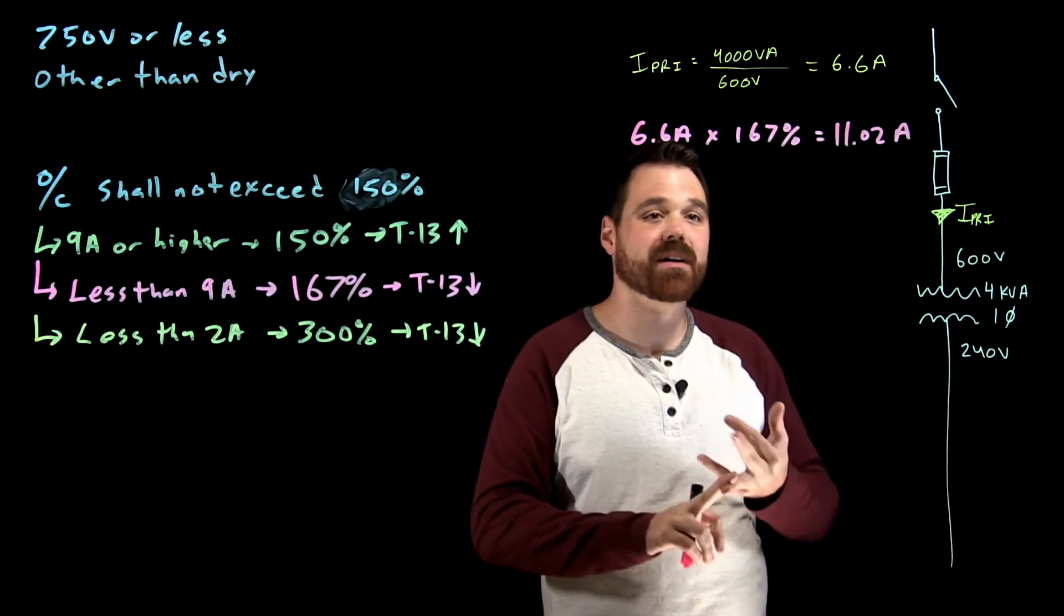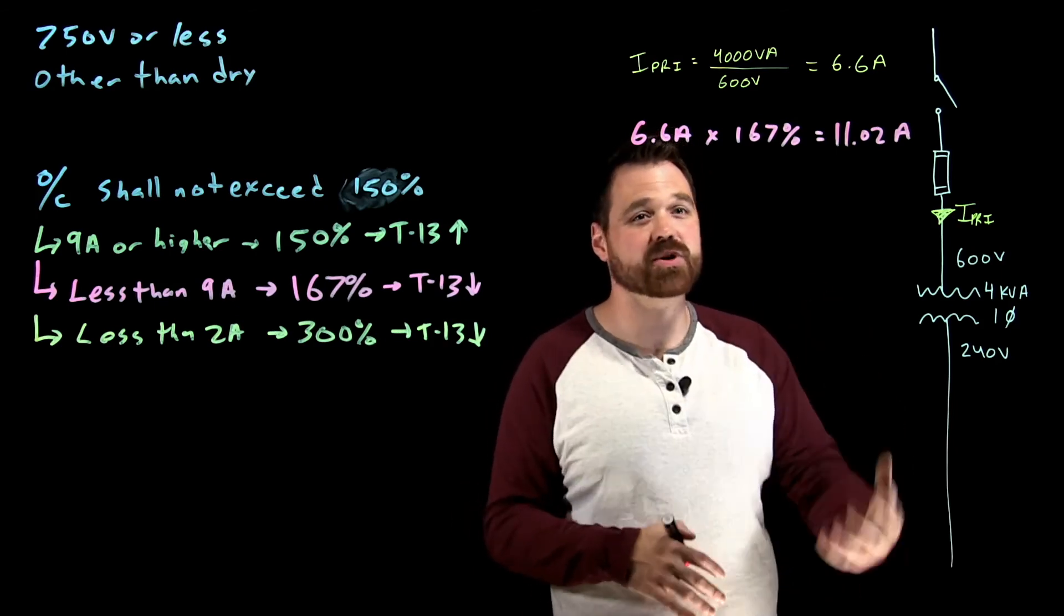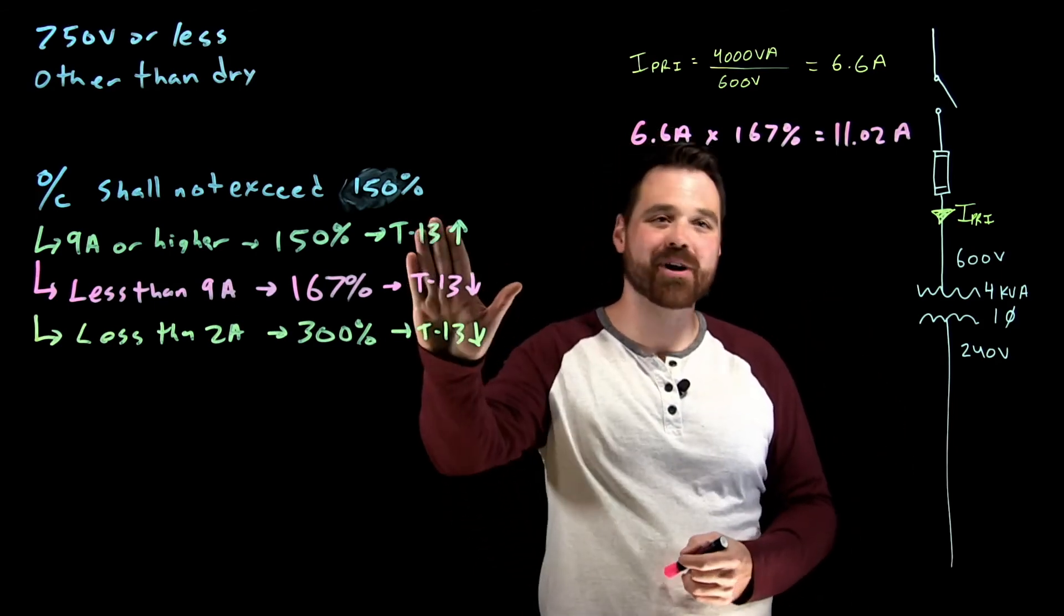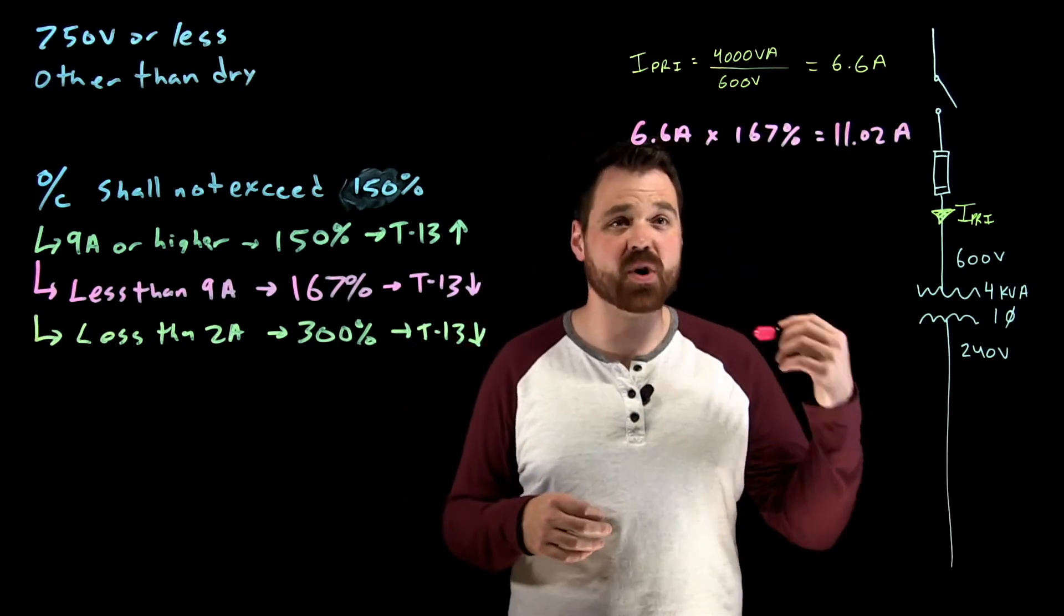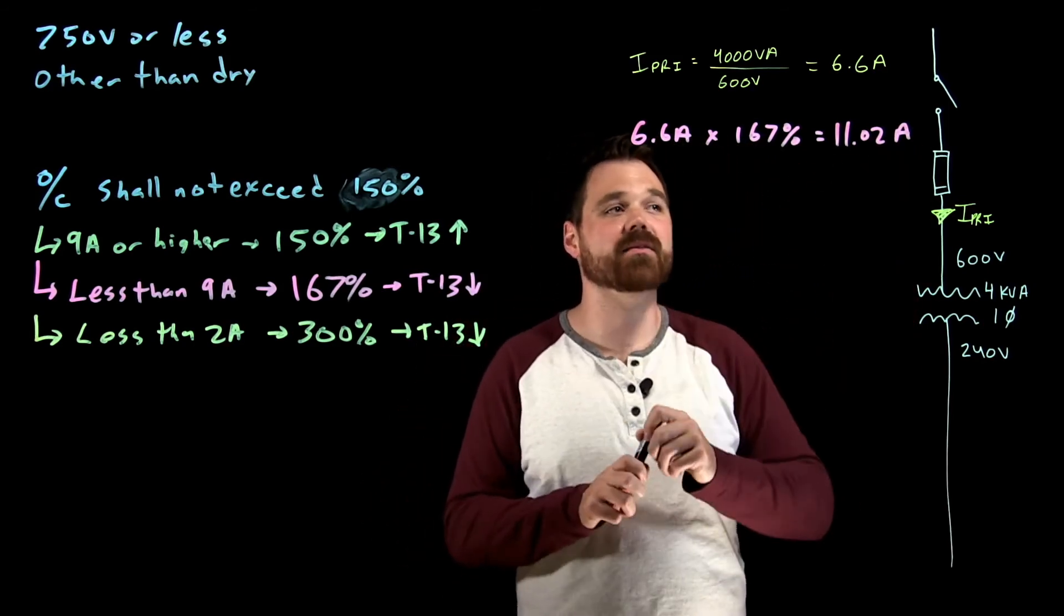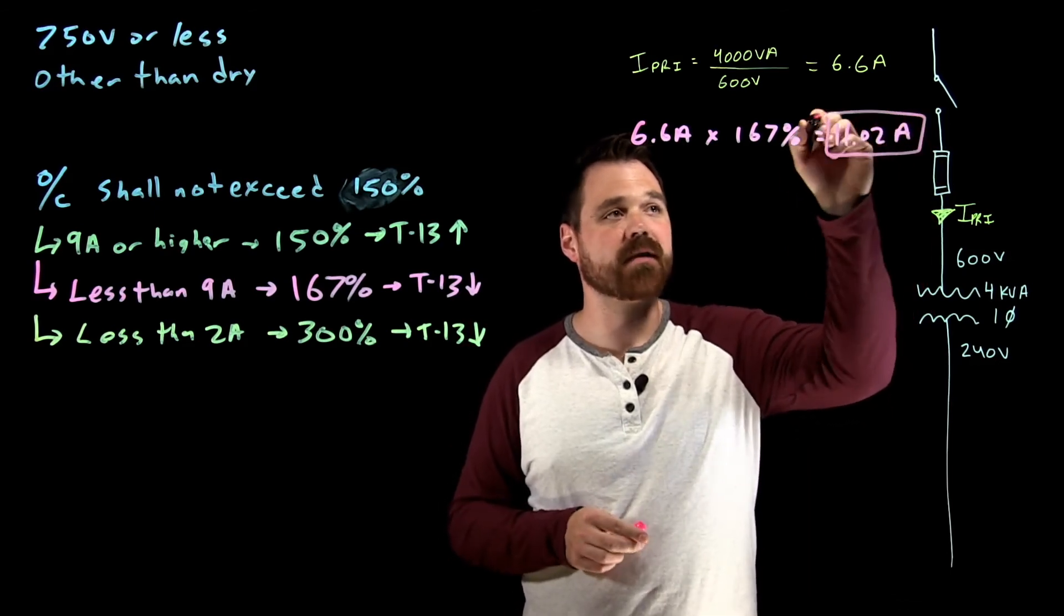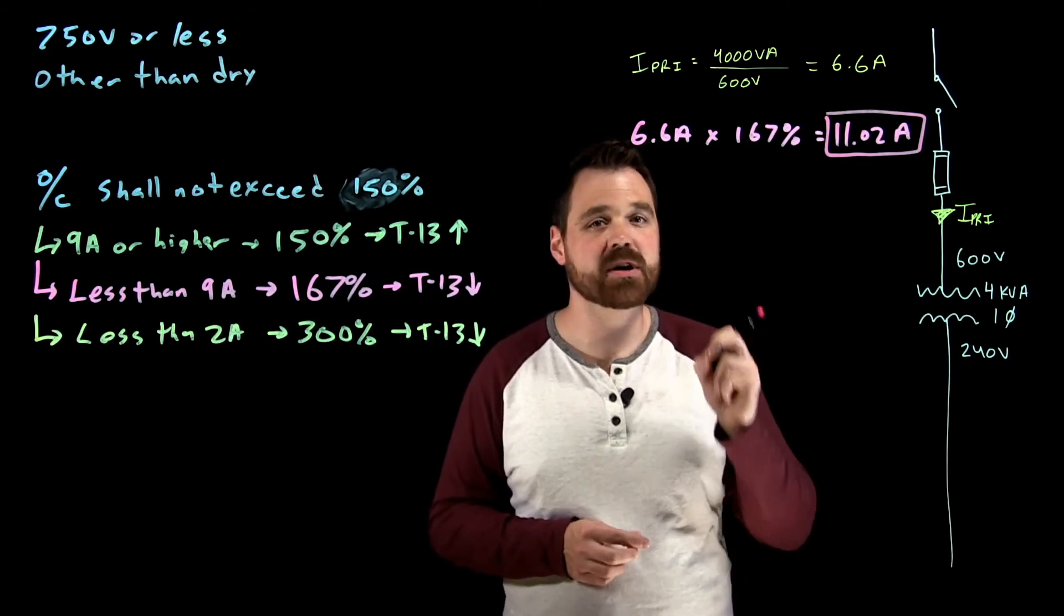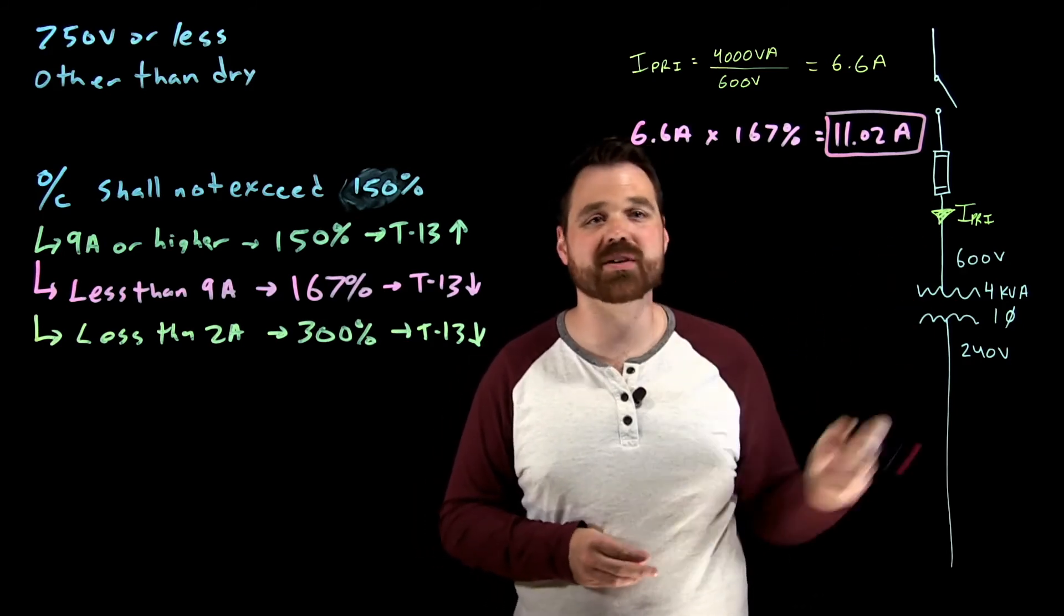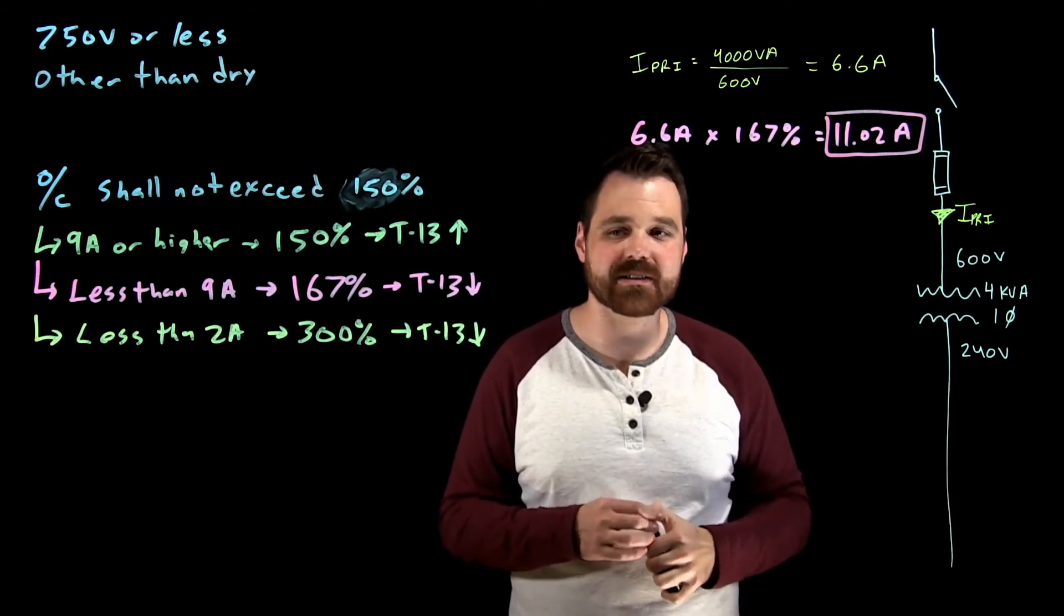Or I'm going to be going down to a 10 amp circuit breaker, which we know is available as well. But what is important here is I cannot go higher than 11.02 amps. 11.02 amps is my maximum rating or setting of overcurrent device. So I cannot exceed that.